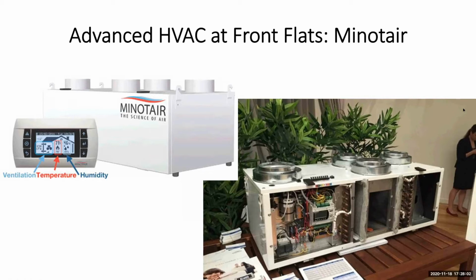Right, well it does have no bottom, so it'll continue in heat pump mode all the way down to whatever. That was one of the things I was calling up about—can it handle negative 25? It says yeah, it handles negative 25 because it's using the heat from the exhaust air. That's an important part—it has a high COP at very cold temperatures because it's pulling heat out of the exhaust air.